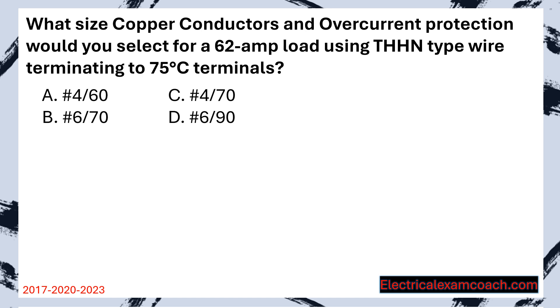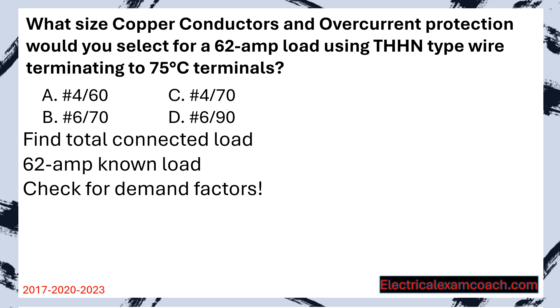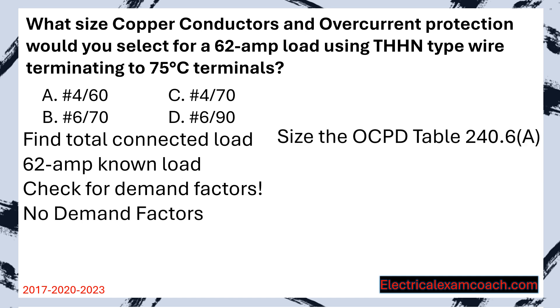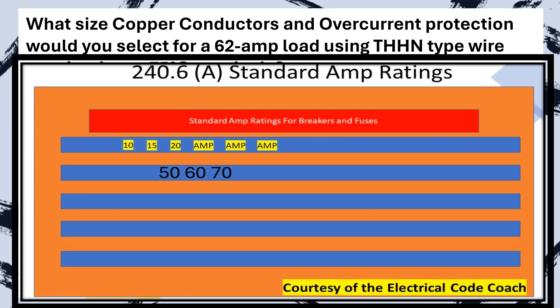What size copper conductor and overcurrent protection would you select for a 62 amp load using THHN type wire terminating to 75 degrees C terminals? Step one: find our total connected load. It starts at 62 amps but we must check for demand factors — with no special pieces of equipment mentioned or the fact that it's running for three or more hours, there are no demand factors. Now we size our overcurrent protective device. We head to our table with a 62 amp known load and choose the next size up, which puts it on a 70.